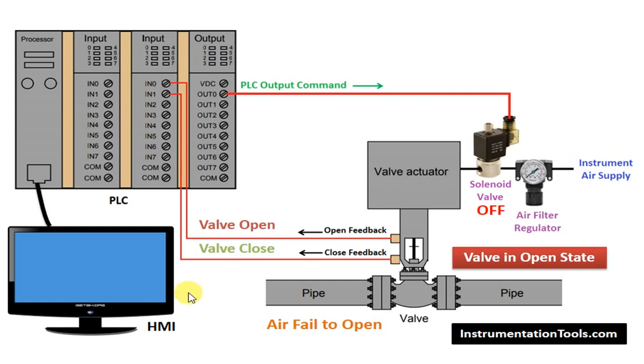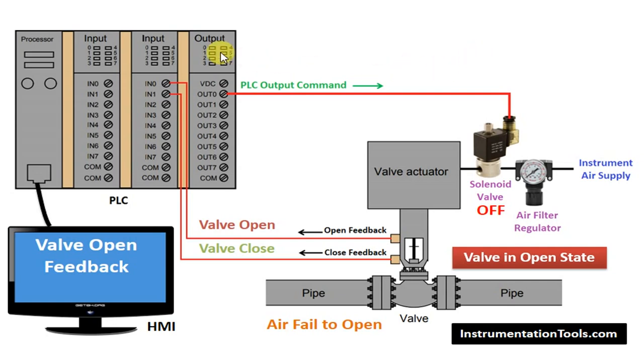In the graphic — say, in the HMI — the valve feedback is shown. Generally, in the graphic, some color changes will be there, like green color. The status of this valve symbol will change to green color, for example. Now let us say the operator gives a close command to the valve. But before that, we will see that the instrument air supply is available here.